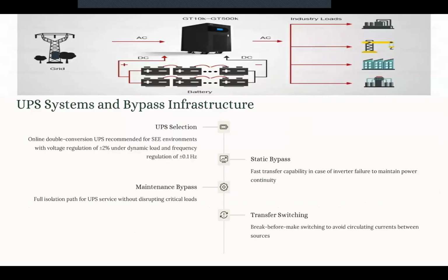Now, we want to create a high quality and reliable power system. So one aspect is to use UPS, uninterruptible power system. The purpose of UPS and those bypass infrastructure is to make sure we have a continuous, clean, and stable power. And we have to make sure that we have those qualities in power during the utility disturbances or sag or outage of the power sources.